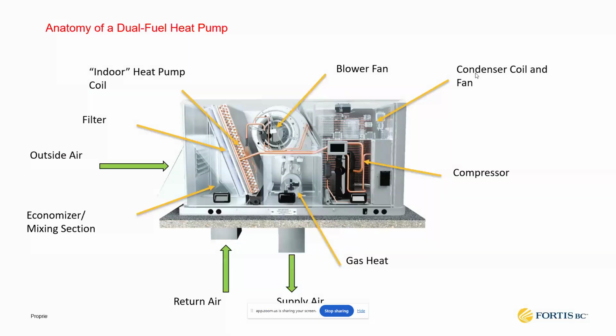So if you think of your typical rooftop unit with a DX cooling and a gas fire section and mixing section and everything, it will be the same. The only difference is that a dual fuel heat pump rooftop unit will be equipped with a heat pump that can provide heating and cooling to the building. And the backup heating will be provided by a gas fire section. Now, how does that work?